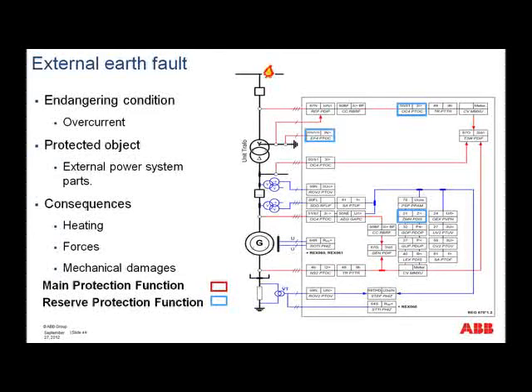If we have an external earth fault, then of course we have the ground fault overcurrent protection here, measured in the star point. We also have the underimpedance, and then depending on the level of the actual phase current for that fault, we have also the phase overcurrent. But all really as reserve protection functions, because primarily for the external fault we would expect to have some busbar protection, or if the fault was close in on the adjacent lines, we would expect to have the primary protection on those objects to clear this fault.